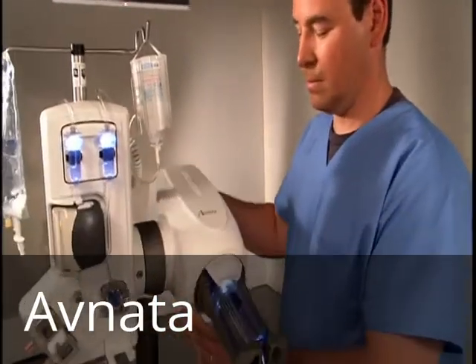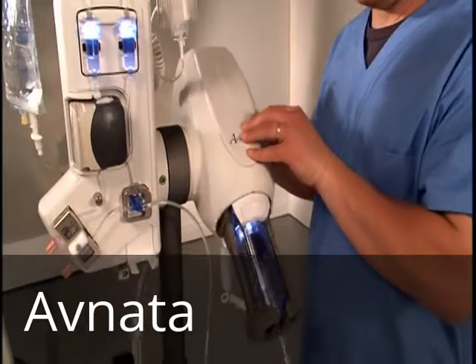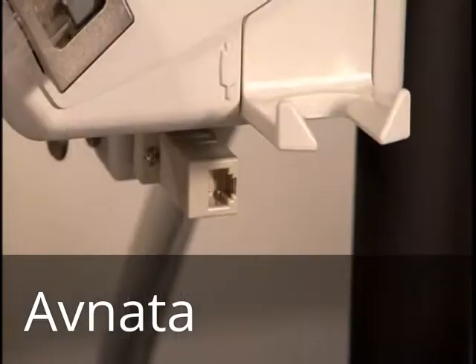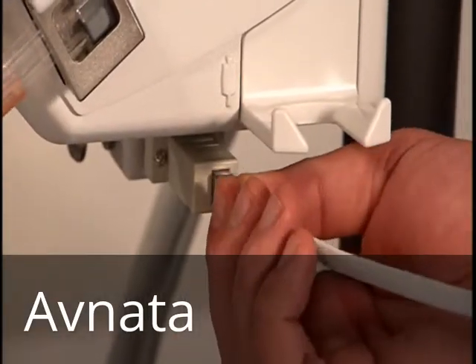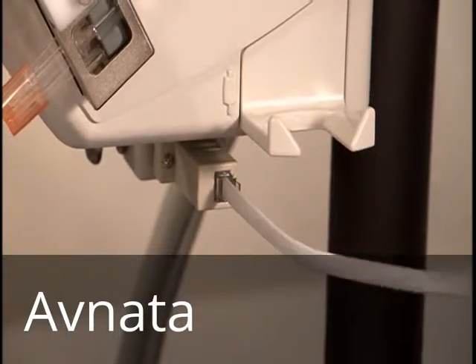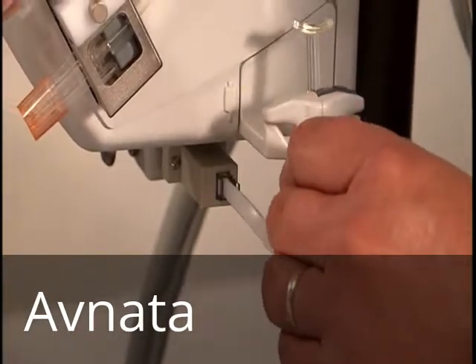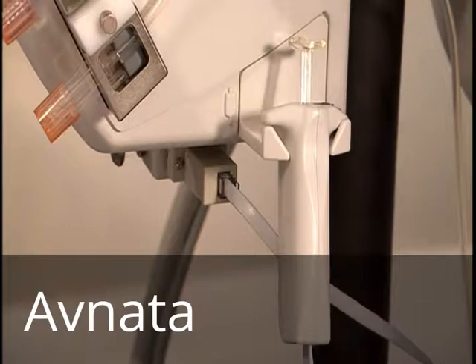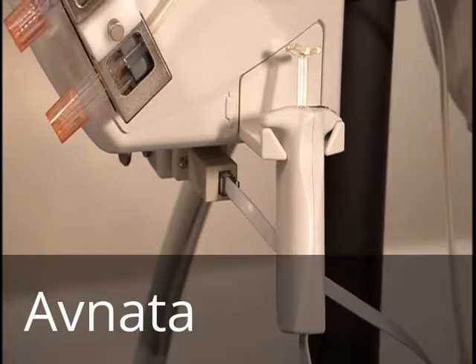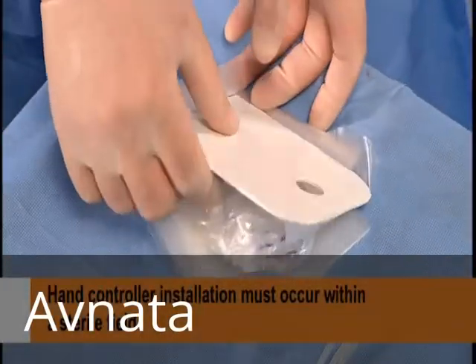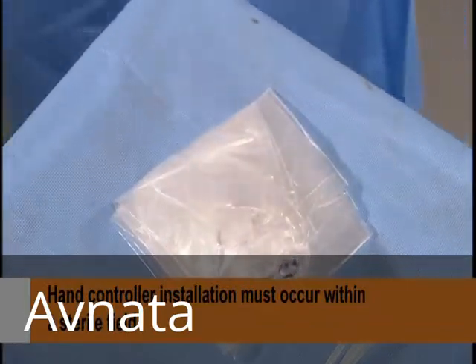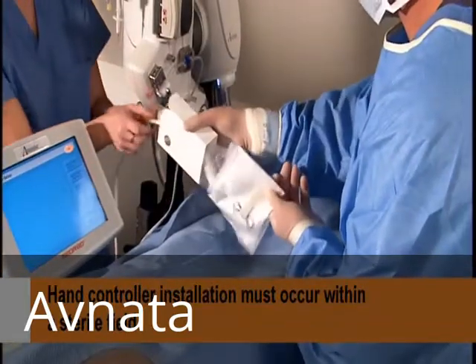Perform Step 6 by rotating the injector head to the down position. Step 7. Install the hand controller on the bottom of the flow control module. The connection works just like a standard telephone jack. Just listen for the click. Hand controller installation must occur within a sterile field to prevent contamination.